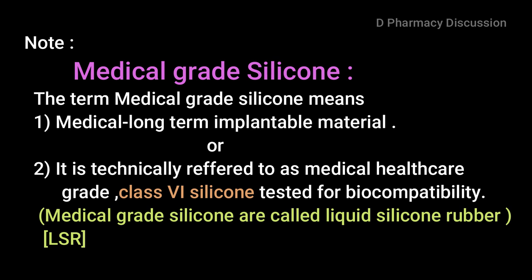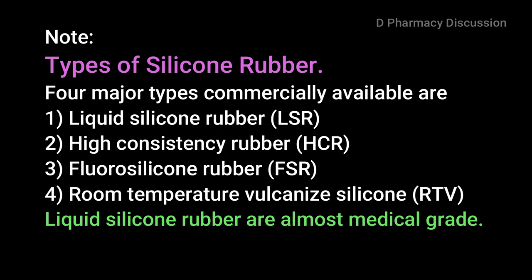The term 'medical grade silicone' means medical long-term implantable materials, technically referred to as medical healthcare grade Class 6 silicone, tested for biocompatibility. Medical-grade silicones are also called liquid silicone rubber (LSR). The four major types of silicone rubber commercially available are: liquid silicone rubber (LSR), high consistency rubber (HCR), fluorosilicone rubber (FSR), and room temperature vulcanize silicone (RTV). Liquid silicone rubbers are almost always medical grade.